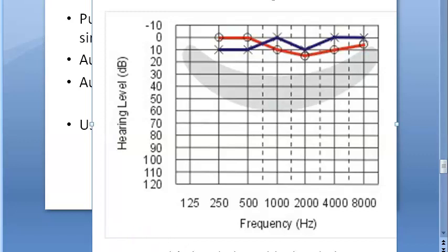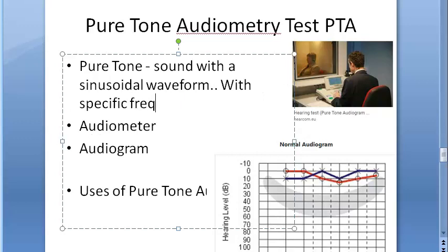Now let us look at the thresholds. For air conduction, the thresholds are measured for tones of 125 Hz, 250 Hz, 500 Hz, 1000 Hz, 2000 Hz, 4000 Hz, and 8000 Hz. For bone conduction, the tones used are 250, 500, 1000, 2000, and 4000 Hz only. Tone here refers to frequency. A pure tone is a sinusoidal waveform sound with a specific frequency, and the audiometer can produce these pure tones with intensity changeable in 5 decibel steps.